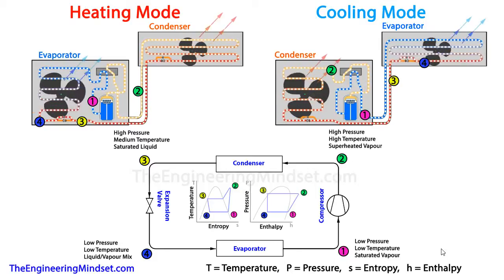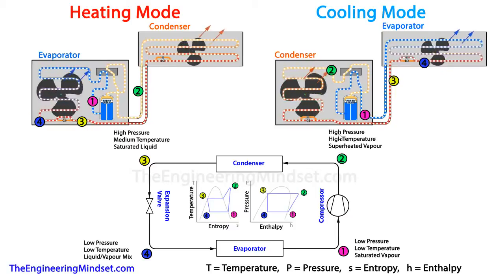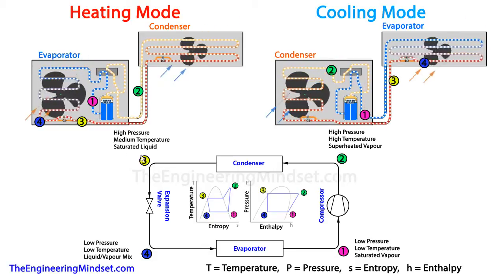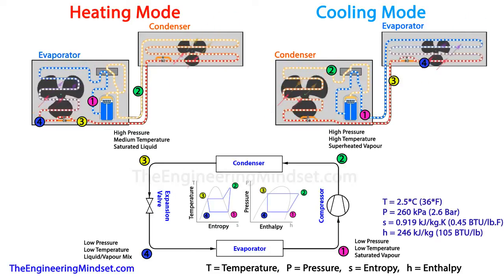Now we can see all the points and what stages the refrigerant goes through. At Point 1 the refrigerant is a low-pressure, low-temperature saturated vapor. At Point 2 it is a high-pressure, high-temperature superheated vapor. At Point 3 it is a high-pressure, medium-temperature saturated liquid. At Point 4 it is a low-pressure, low-temperature liquid-vapor mix, which then makes its way back to Point 1.